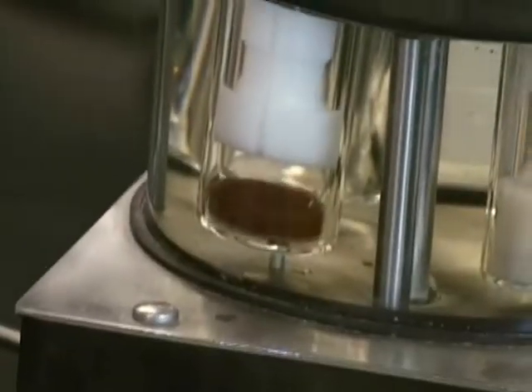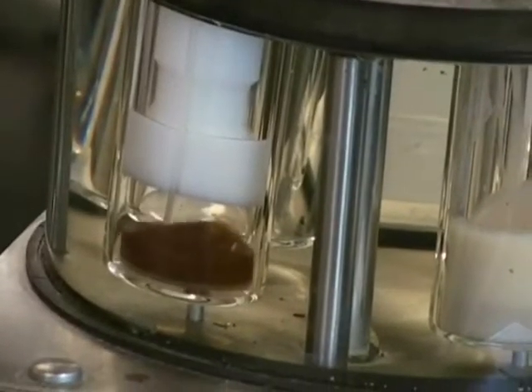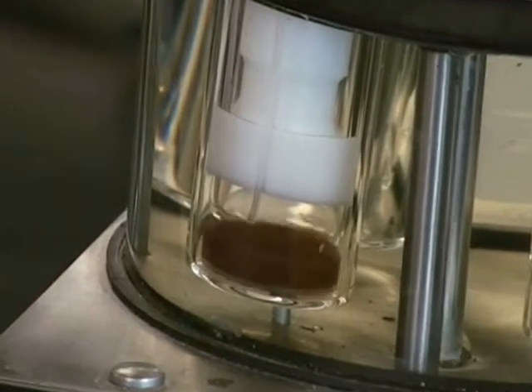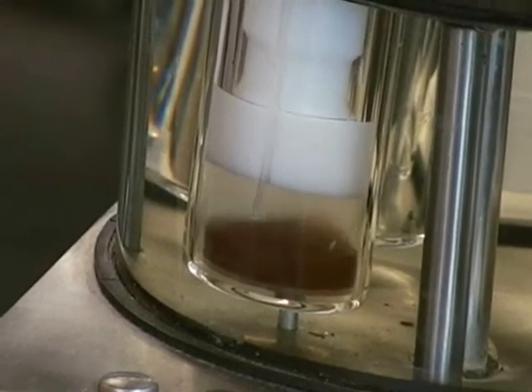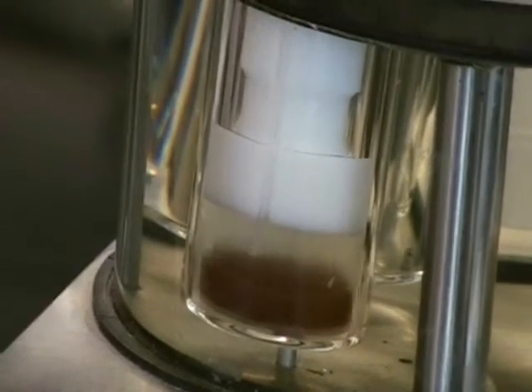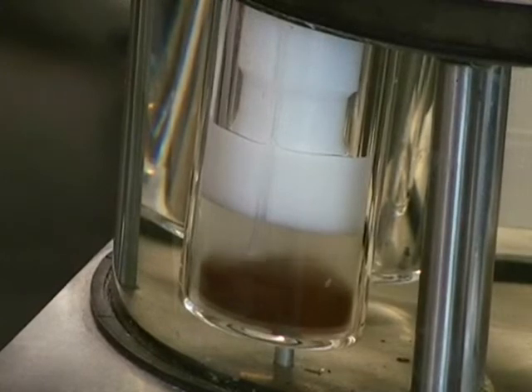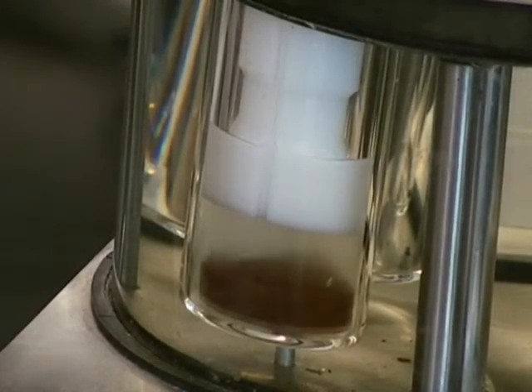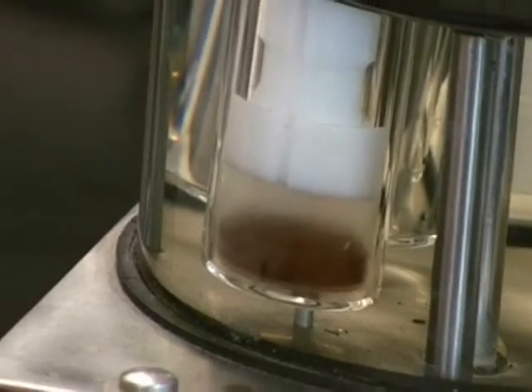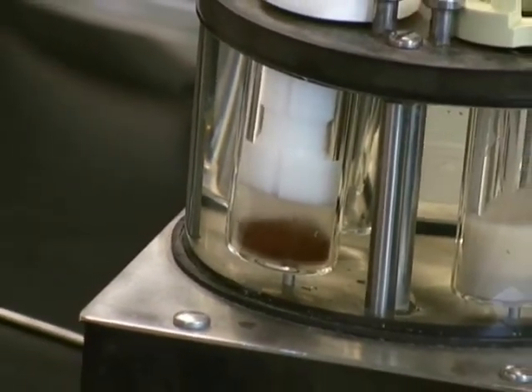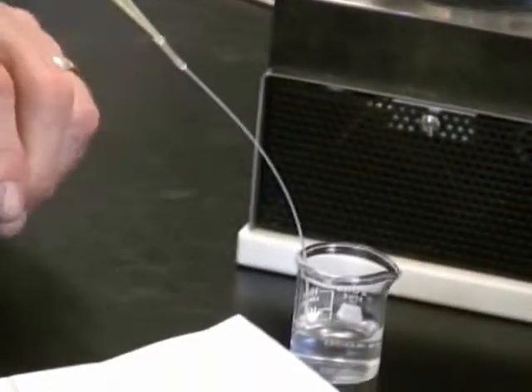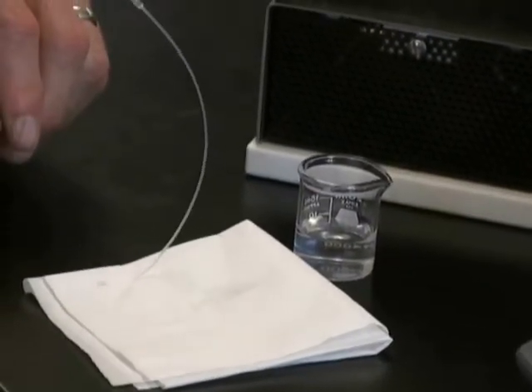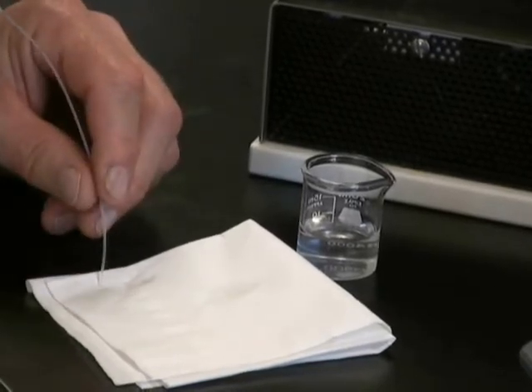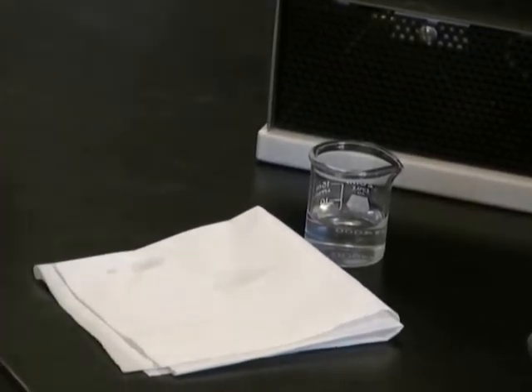Take the capillary, guide it into the slot, push it in until about halfway into the chamber. Then you add the yeast. You add slowly. You do not use the second stage. When you reach the first stage, you keep it compressed, withdraw the capillary, expel the last quantity, and right away rinse. So when you're adding the yeast to the chamber, if you use the second stage, you'll be injecting air into the system. And it's imperative that we only have the oxygen or the air that's dissolved in the buffer.